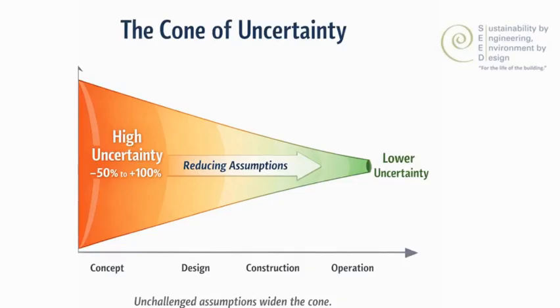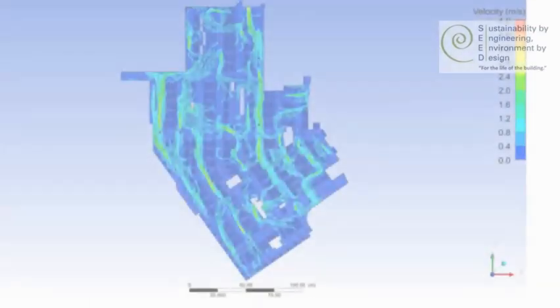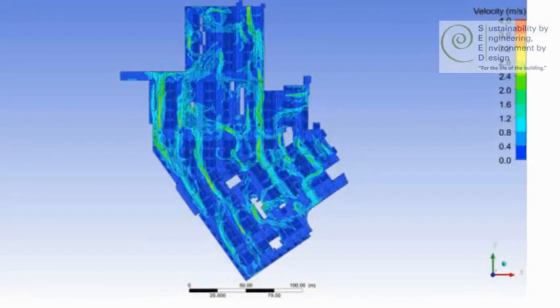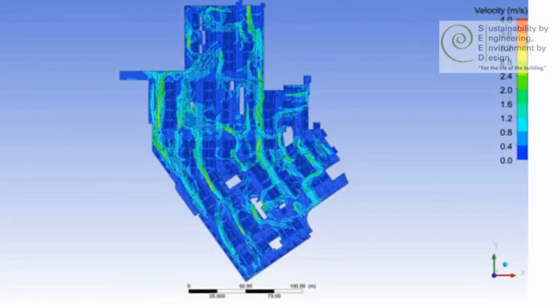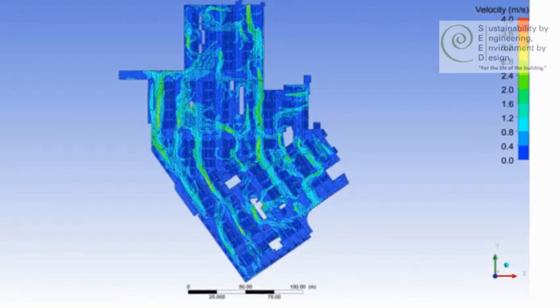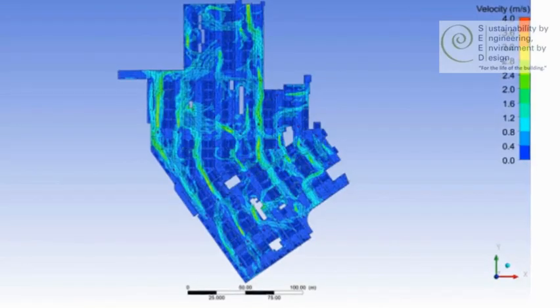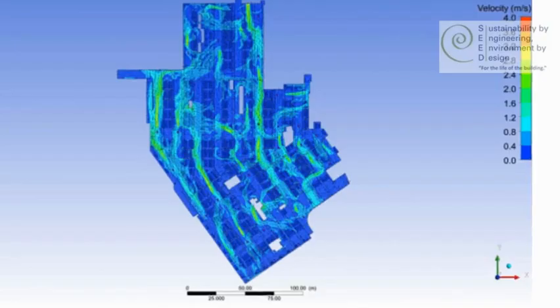So trying to resolve as many of those assumptions during the design phase before construction is important. Another risk that you face is the use of fan suppliers. Don't get me wrong, they are capable of CFD modeling, but they can often produce results like this one here, where air is blowing 60 and 80 meters almost effortlessly. Don't be fooled, air does not move like a tennis ball. This is an incorrect setting on the CFD machine.